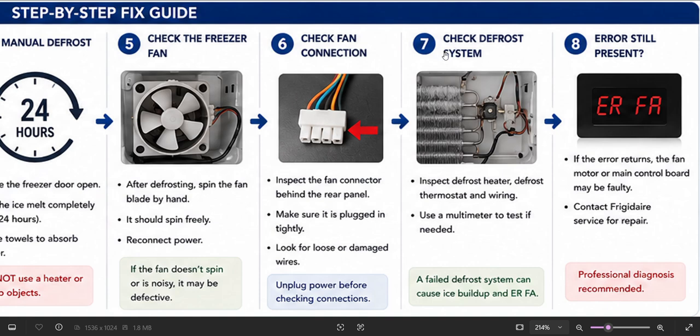Step 7. Check the defrost system. Inspect the defrost heater, defrost thermostat and wiring. Use a multimeter to test if needed. A failed defrost system can cause ice buildup and the error.